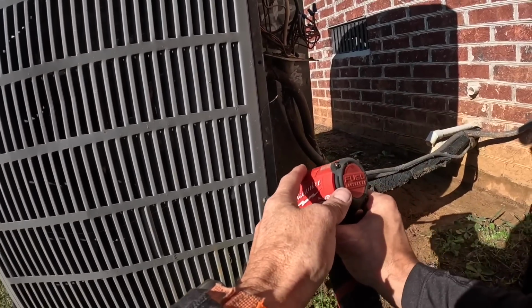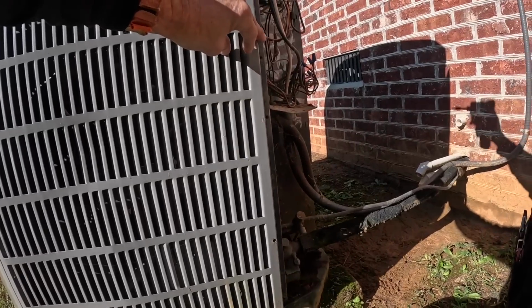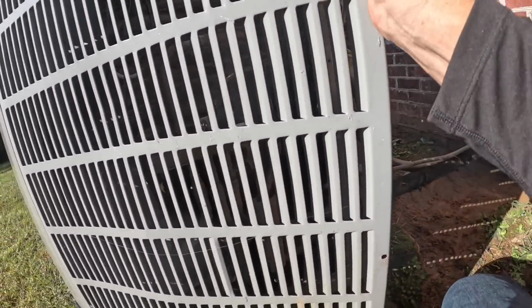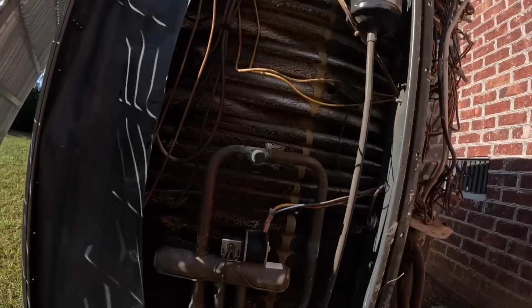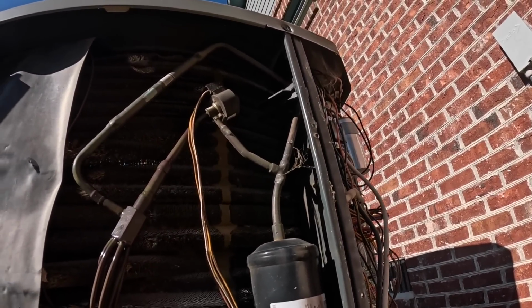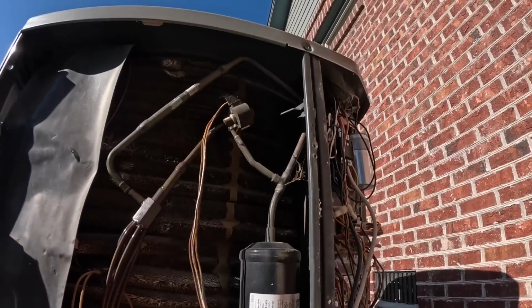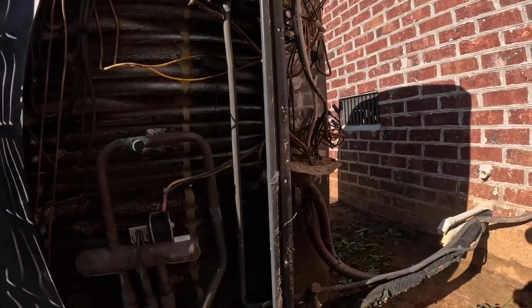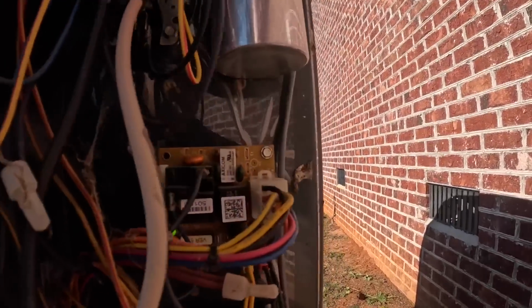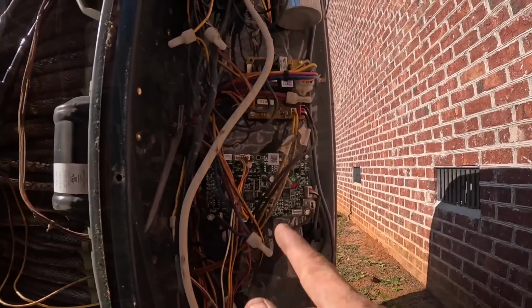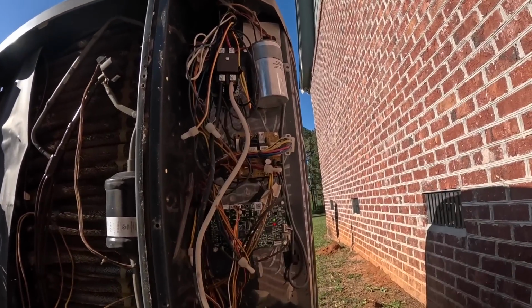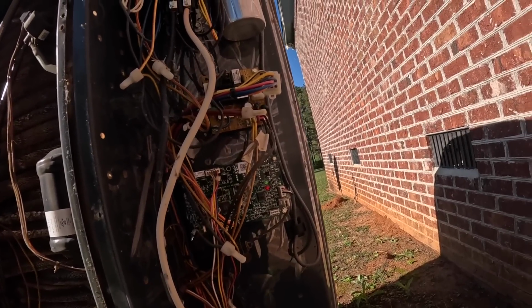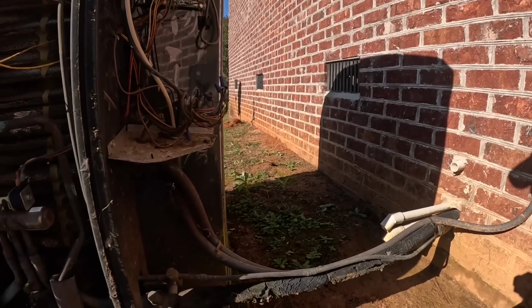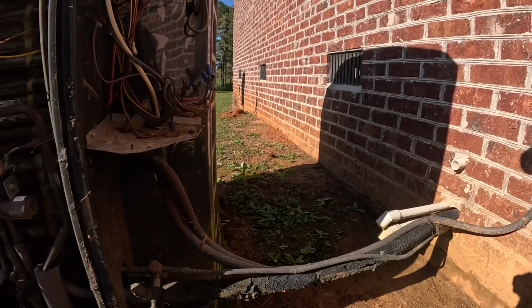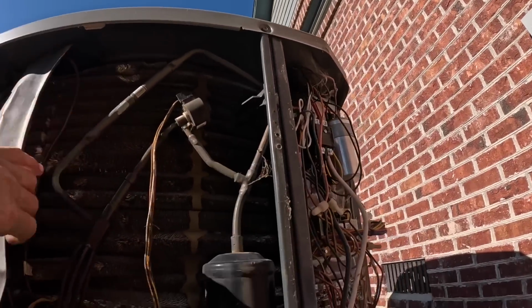Let's take this off and see what I got in here. All right, we got an electronic expansion valve. I'm going to have to reset this, and I think I do that by just unplugging one of these. Before I even try to get this back going, let's probe up on this and see if that error code is right. I don't see any sensors on the liquid line. I mean, that's it right there.